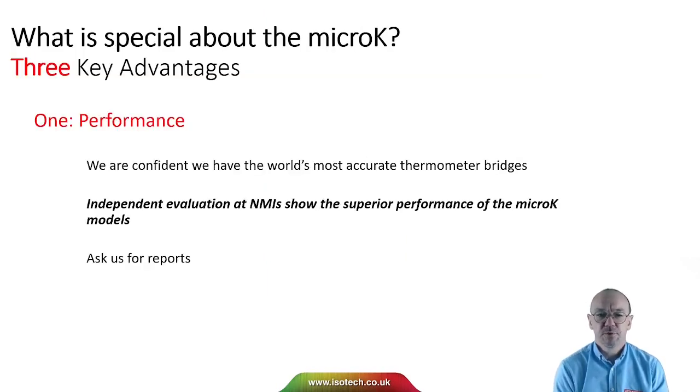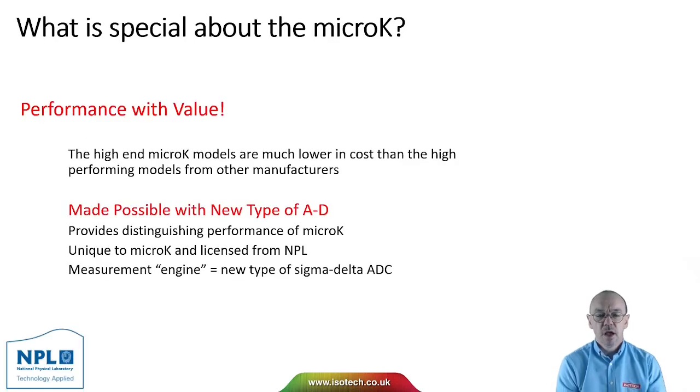We believe the micro-K is very special and I'd like to tell you about three key advantages. First is performance — we are confident we have the world's most accurate thermometer bridges, and independent evaluation at NMIs demonstrates the superior performance of the micro-K models. Also, the higher-end micro-K models are much more affordable than competing models, made possible by a new type of sigma-delta converter whose technology we licence from the National Physical Laboratory in the UK.